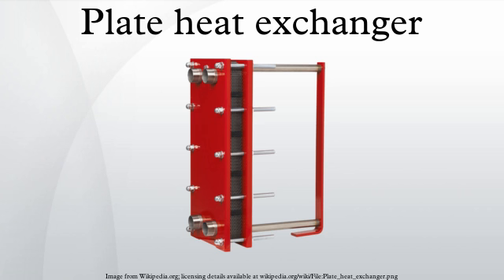Evaluating plate heat exchangers. All plate heat exchangers look similar on the outside. The difference lies on the inside, in the details of the plate design and the sealing technologies used. Hence, when evaluating a plate heat exchanger, it is very important not only to explore the details of the product being supplied, but also to analyze the level of research and development carried out by the manufacturer and the post-commissioning service and spare parts availability.